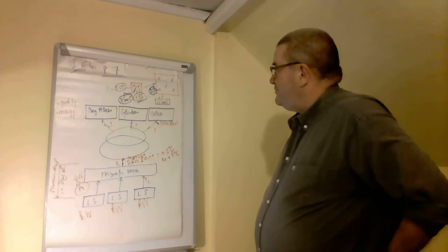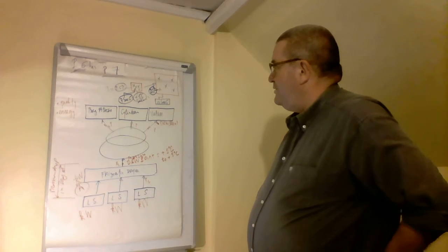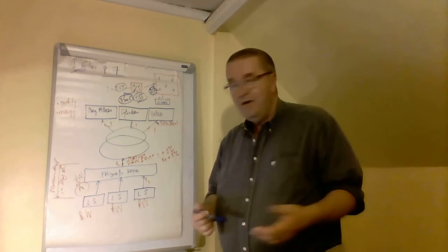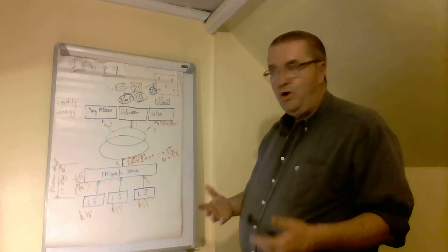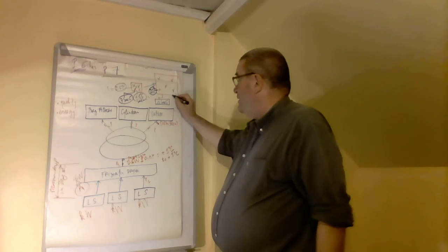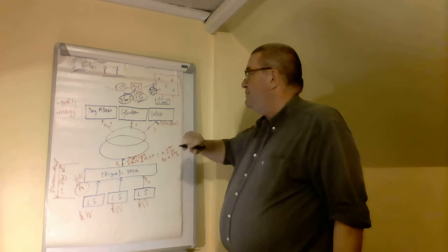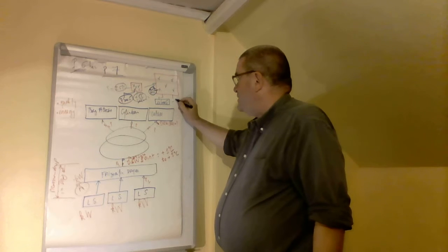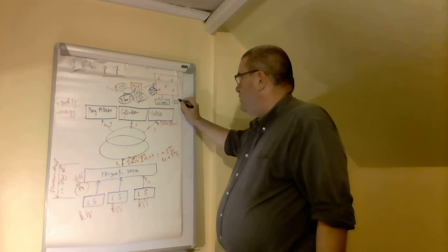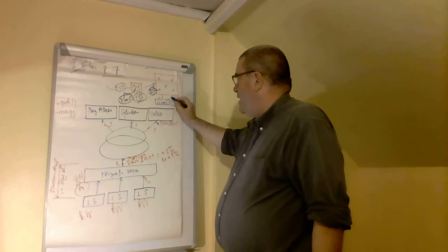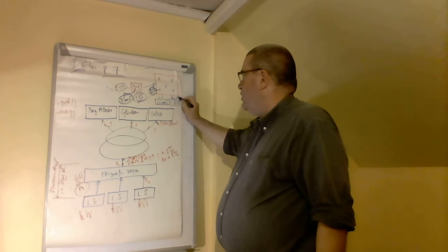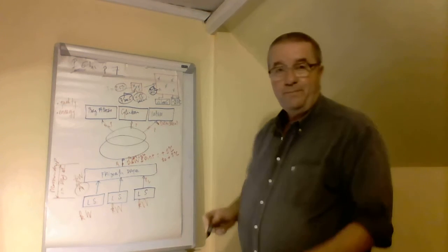So you have dried your air, the concentration in steam for each unit of volume is much lower. So what you measure here is you were at +1, you will be at -20 or 22 or something like that, Celsius. And this is the atmospheric dew point temperature.